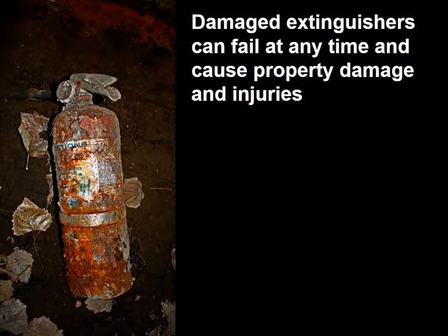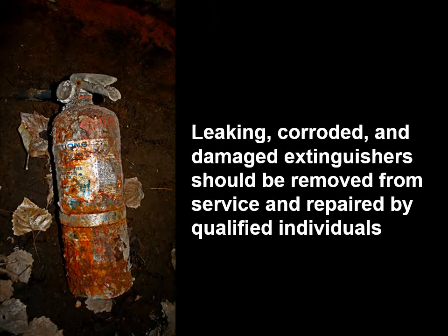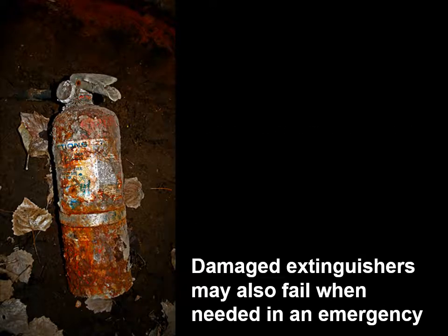Damaged extinguishers can fail at any time and cause property damage and injuries. Leaking, corroded, and damaged extinguishers should be removed from service and repaired by qualified individuals. Damaged extinguishers may also fail when needed in an emergency.